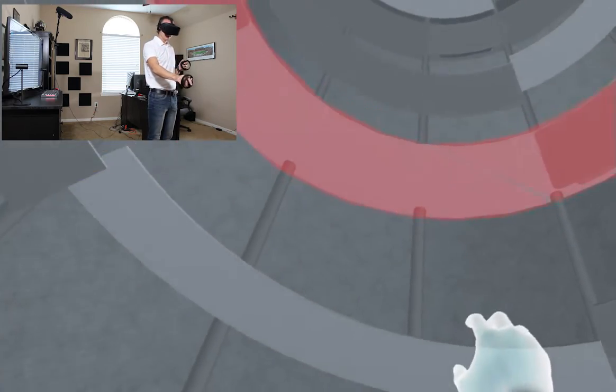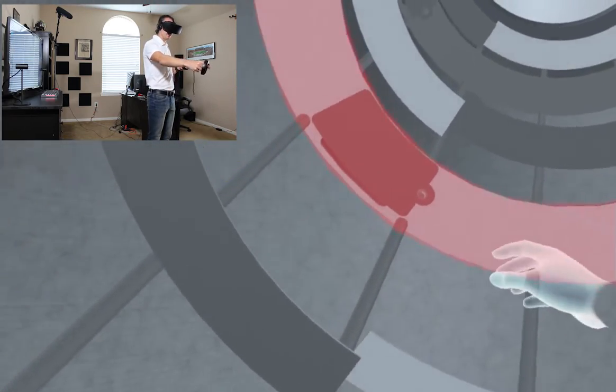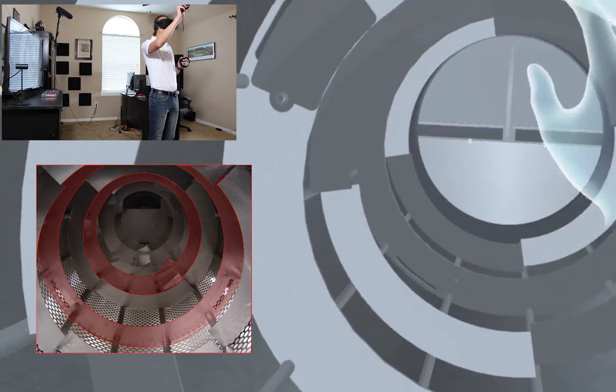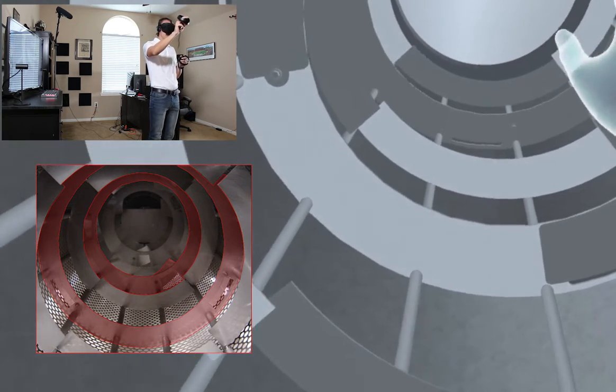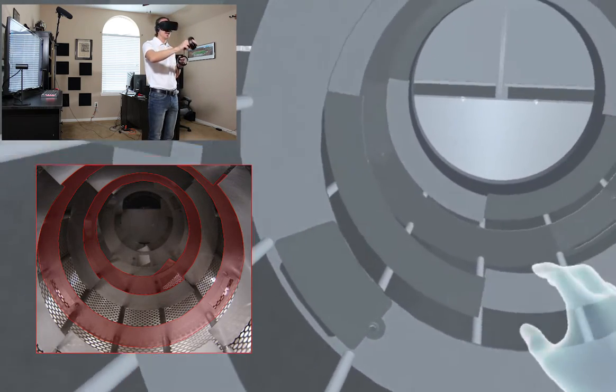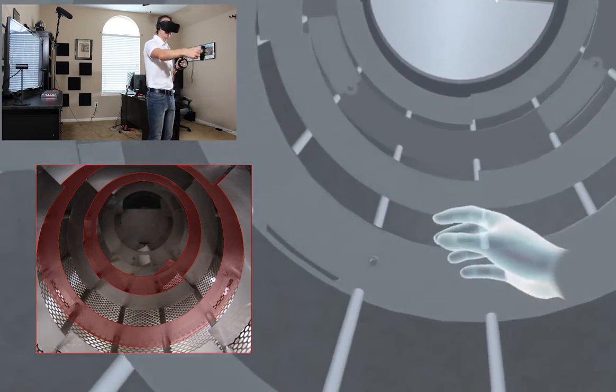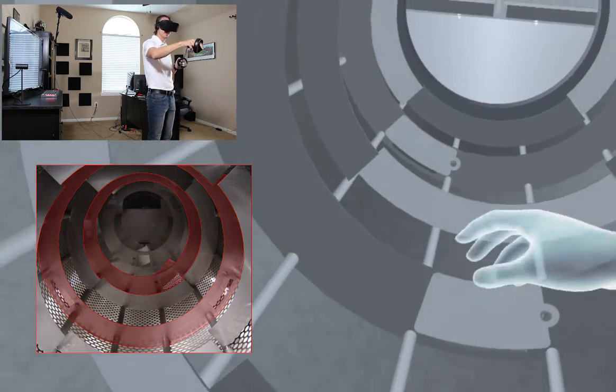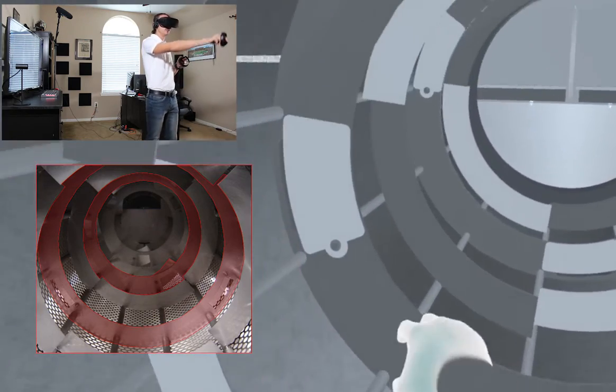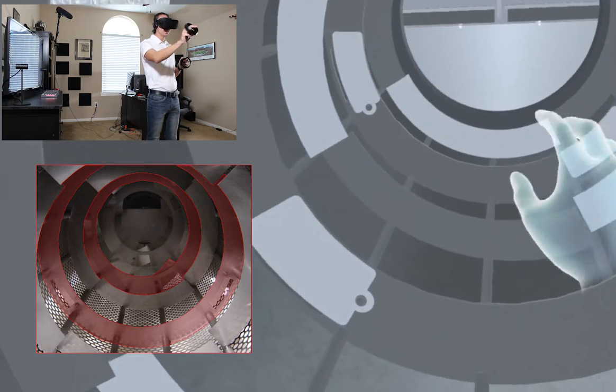So they look like flights, which induce sludge movement down the drum, but they do the opposite. They actually retain the sludge in four sections within the drum, and the sludge actually has to overflow each one of these split augers. So you can see that it goes all the way around.